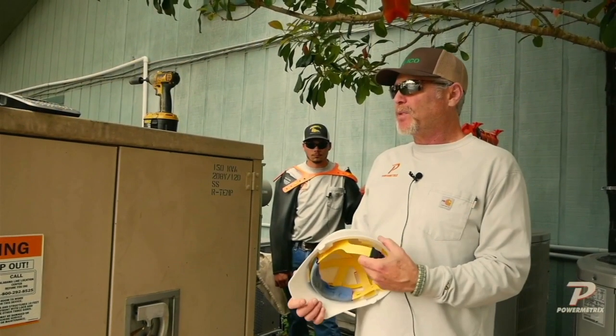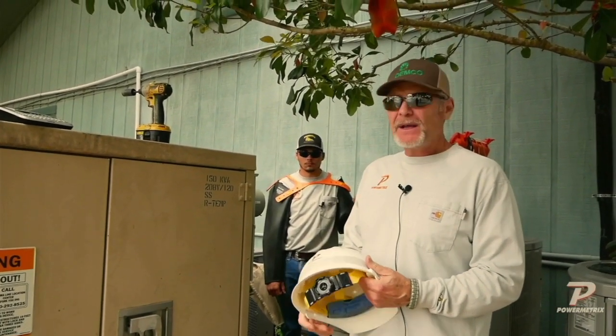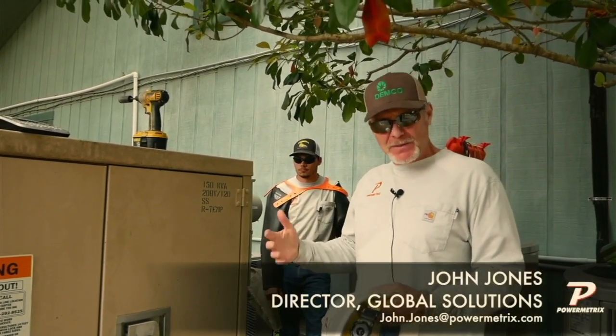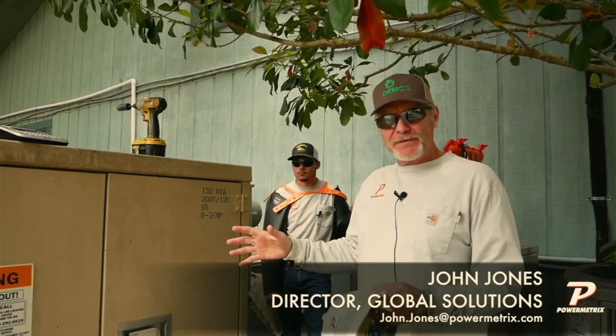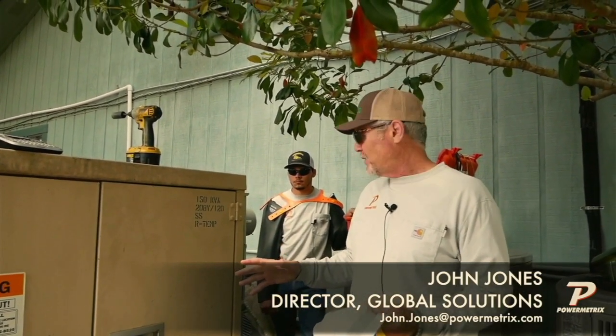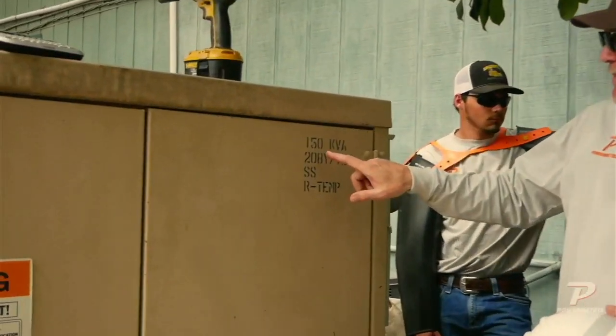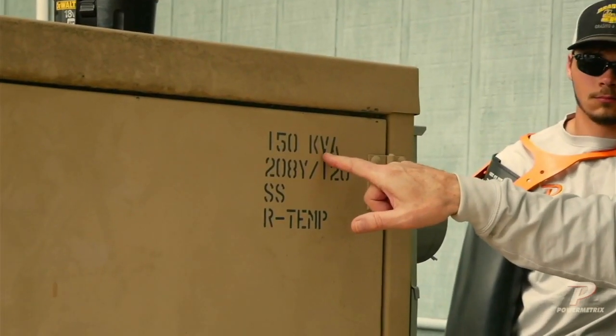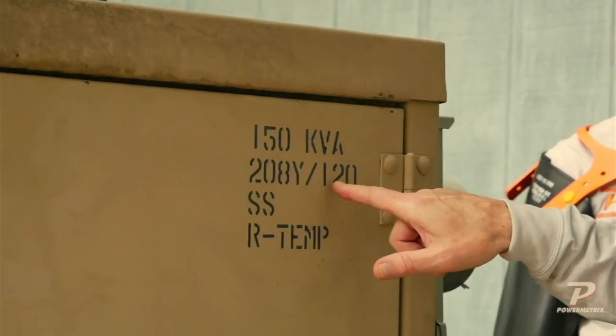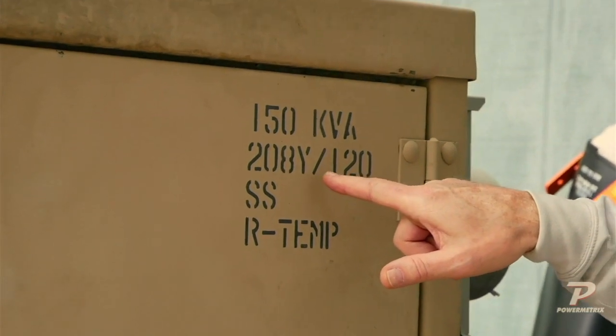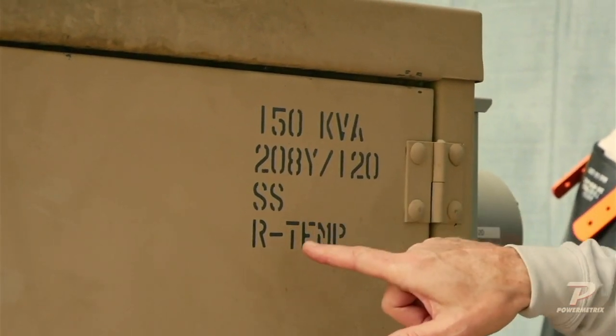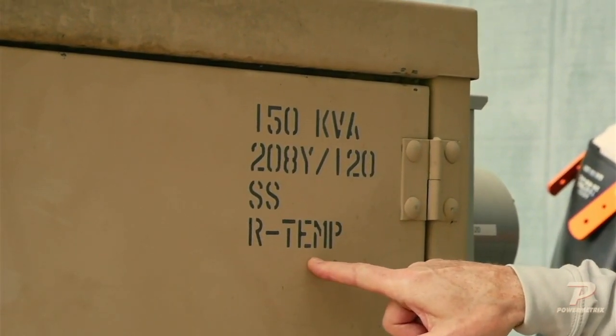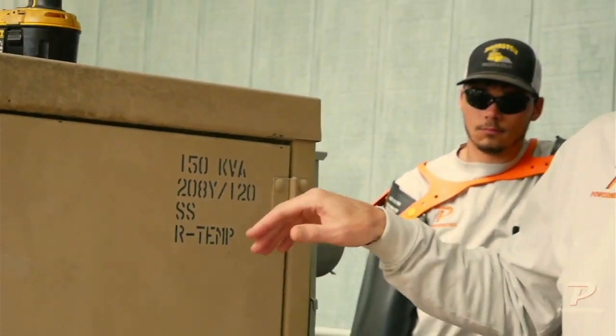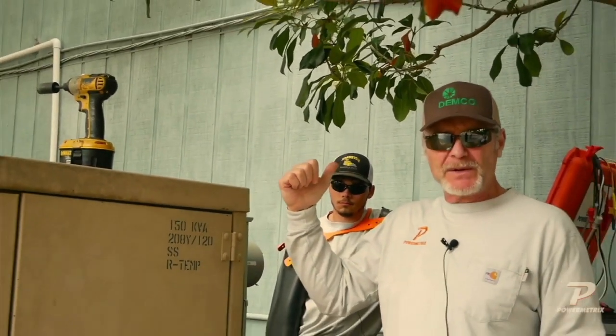Now Brian and I are going to test a pad mount here, and we're going to go through that same inspection process, but we can learn a few things first. Looking on the outside of this pad mount transformer, we can see it's 150 kVA, and we'll know our system already before we get in there. It's a 208Y/120. It says R temp, which means it's got a different oil rating because of how close it is to the building.